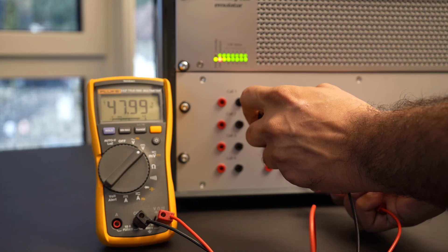Now let's validate the BMS cell balancing. To do that, we recreate a charging scenario by switching the BMS from standby to charging mode with a charge current of 5 ampere. We see that the module SOC and the SOC of various battery cells increase accordingly. By inspecting the BMS data, we see that the current charge imbalance across 12 cells is about 75 millivolts. The BMS is configured to start balancing if the imbalance crosses 100 millivolts.